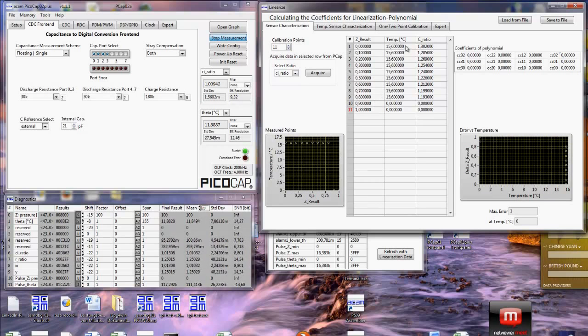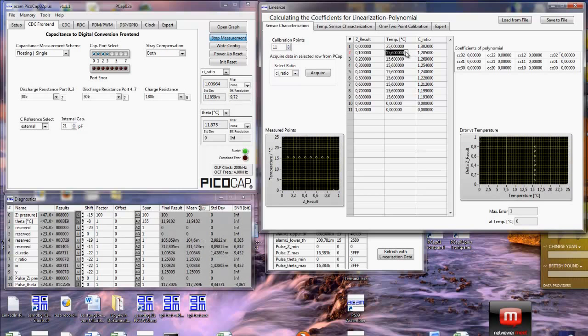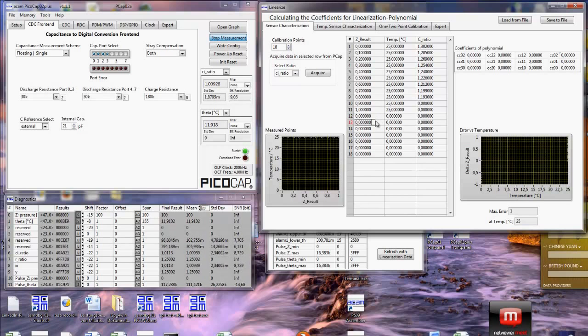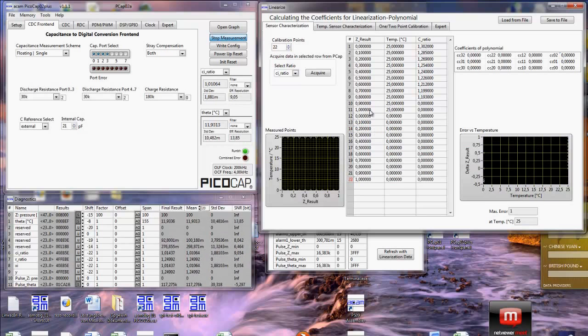Then next you would set the temperature where you want to take the measurements from. So in my example I would set this to 25 centigrade. And of course I can do the same now for a second temperature, which simply means to add more calibration points and do the same again. So I start here with 0 and then go up to 10% and so on. And in this case, of course, I want to calibrate at another temperature. That means I set here, for example, 60 centigrade in my example, and do that for the whole row again.